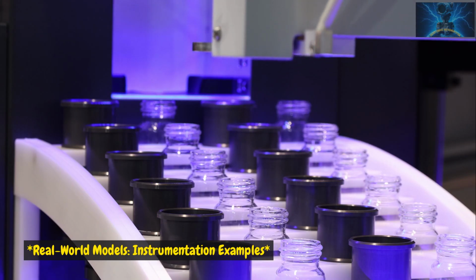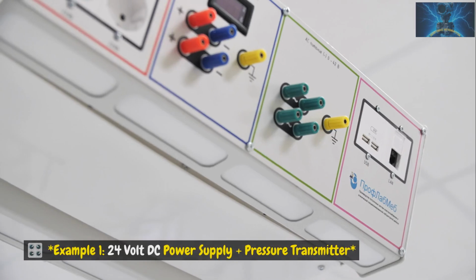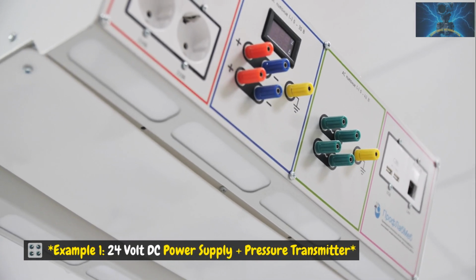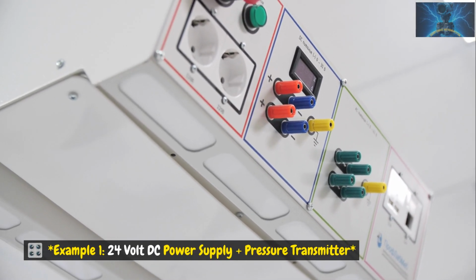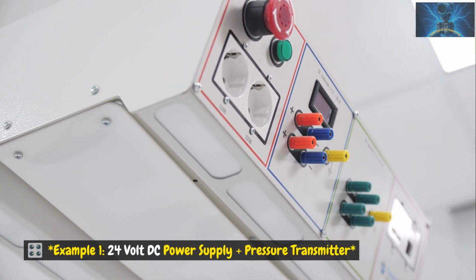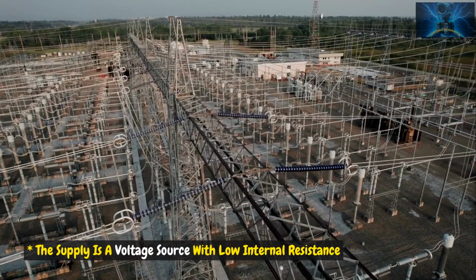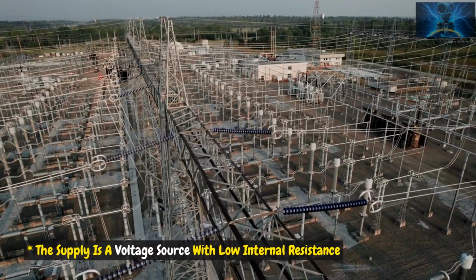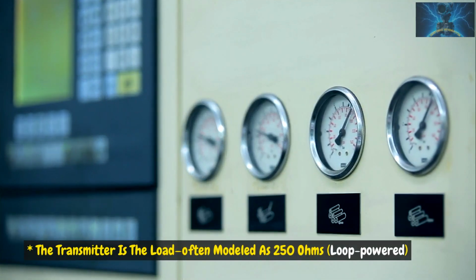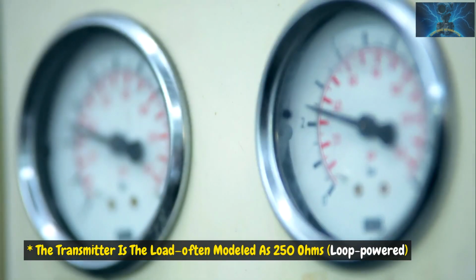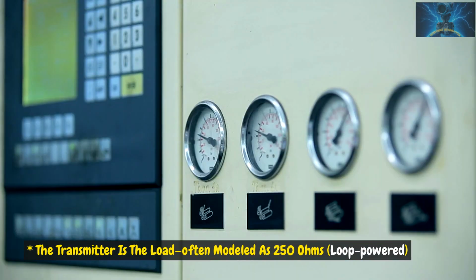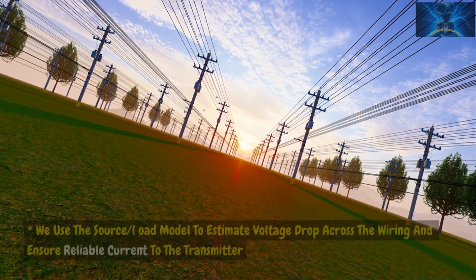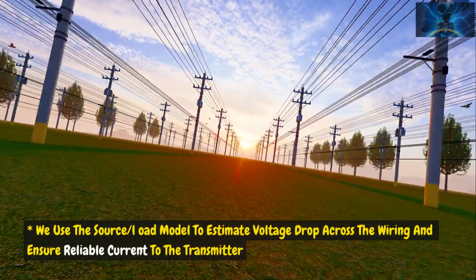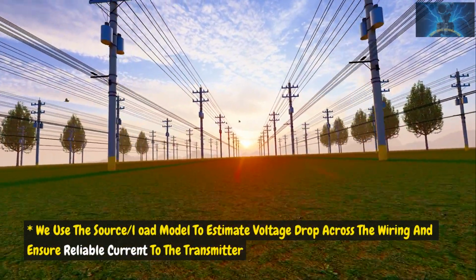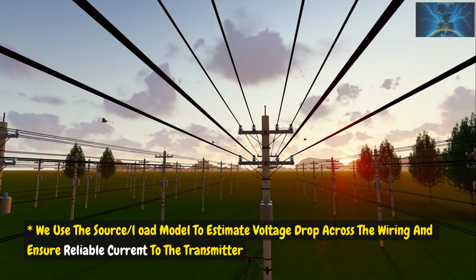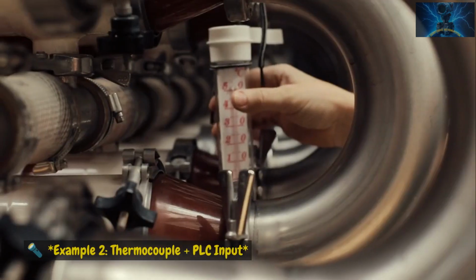Real-world models, instrumentation examples. Example 1: a 24-volt DC power supply plus a pressure transmitter. The supply is a voltage source with low internal resistance. The transmitter is the load, often modeled as 250 ohms, loop-powered. We use the source-load model to estimate voltage drop across the wiring and ensure reliable current to the transmitter.